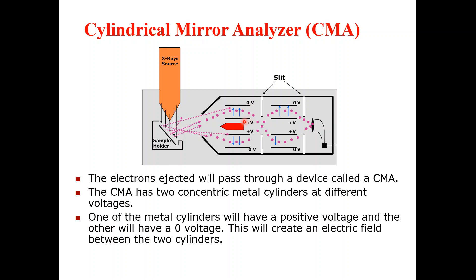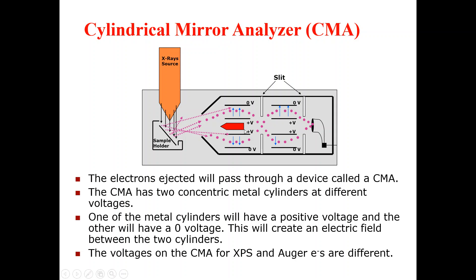The main purpose of this arrangement of the cylinders is that it will create an electric field between the two cylinders. One cylinder has been put at zero voltage and the other at positive voltage. The purpose of this voltage difference is to create an electric field between the two cylinders. Note that the voltage on the CMA for XPS and Auger electrons are different from one another.